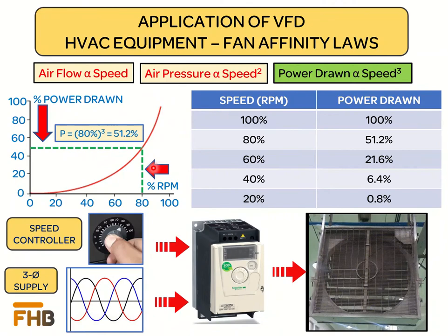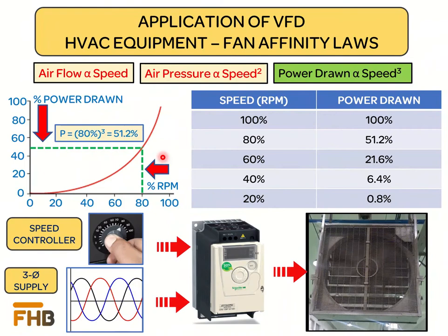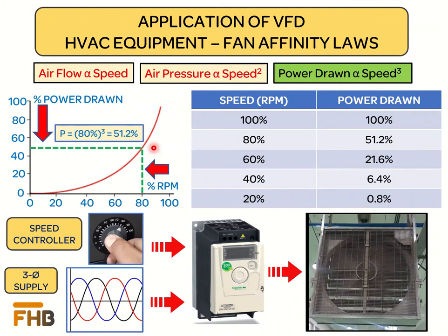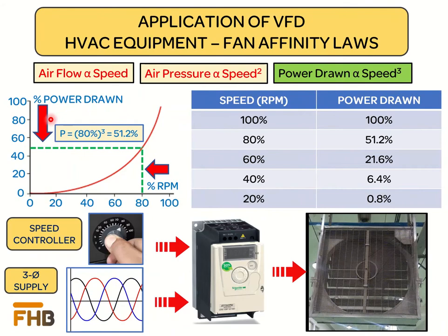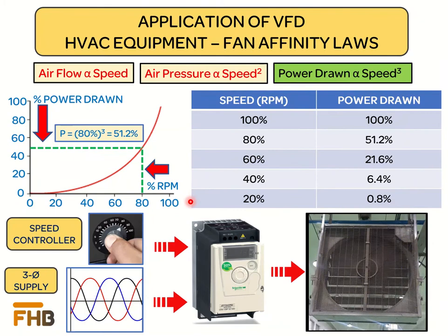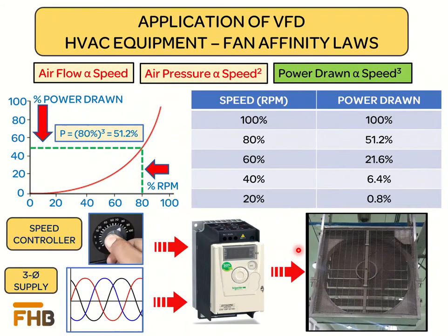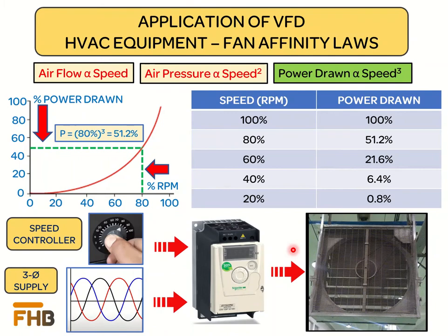We do not need to run fans at 100% speed at all times. We can adjust the speed of the fan based on the required airflow. For instance, if we reduce the fan speed from 100% to 80%, the power drawn will be reduced to nearly 50%, which is a very significant saving on the electricity bill. Reducing speed to even lower values will save more power, as shown in the table. The circuit implementation for this speed control is very simple — we provide the VFD three-phase power and the desired reference speed value, and the VFD provides the fan motor a waveform that drives it at the desired speed.